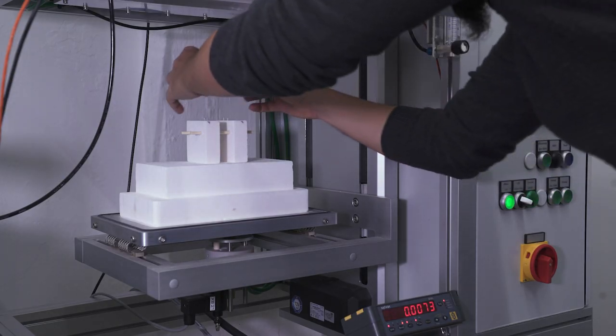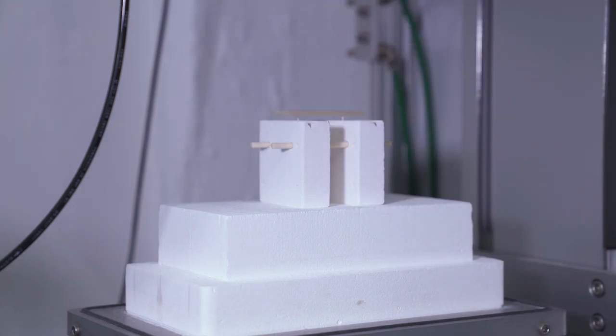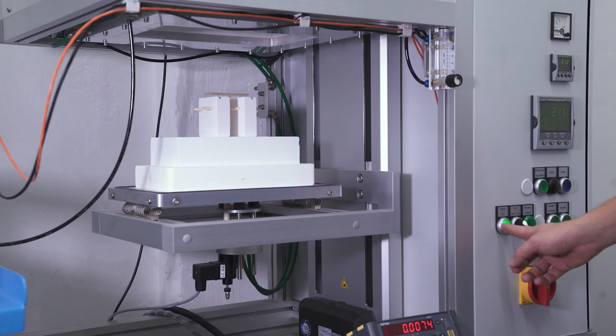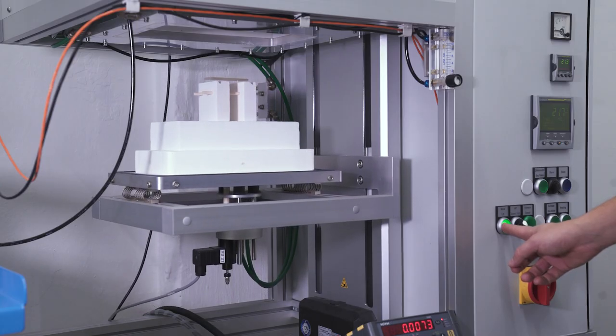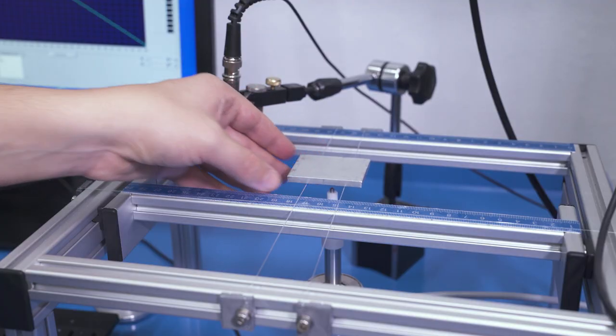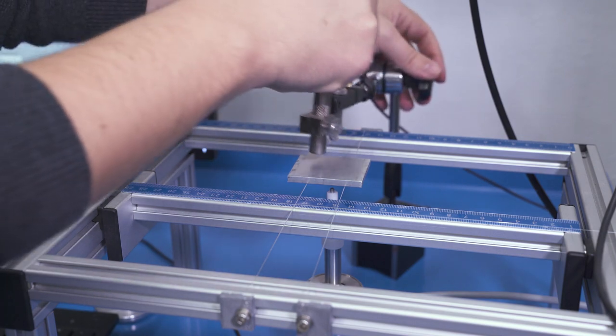Non-destructive tests based on impulse excitation technique for measurement of young modulus, shear modulus, Poisson ratio and internal friction damping up to 1600 degrees Celsius. It acts as quality control tool by comparing resonant frequencies. It works also as a dynamometer.